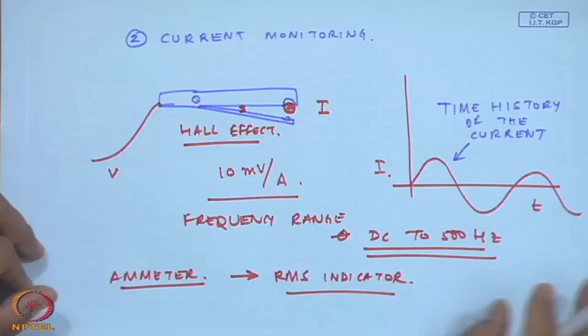Once I get the time history of this current, the entire waveform is available with me. So, with a signal analysis system, I can do the current spectrum analysis and try to know whether sidebands are there or not. This becomes a very convenient way to measure the condition of the electrical motor rather than doing a vibration monitoring. If I do a vibration monitoring, I am not sure that I will always get sidebands around the supply frequency. That may not happen. I may see only the peaks at supply frequency and twice supply frequency.